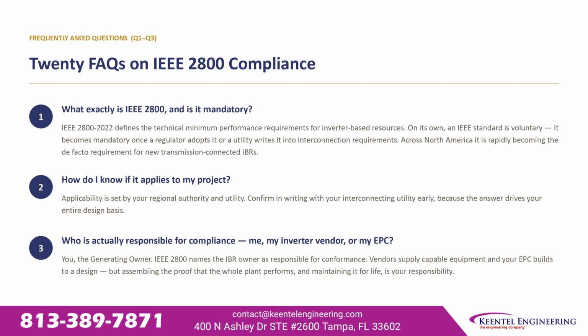How do you know if it applies to your project? Applicability is set by your regional authority and your utility. Confirm it in writing with your interconnecting utility early, because that answer drives your entire design basis. Who is actually responsible for compliance? You, your inverter vendor, or your EPC? It's you, the generating owner. IEEE 2800 names the IBR owner as responsible for conformance. Vendors supply capable equipment, and your EPC builds to a design. But assembling the proof that the whole plant performs and maintaining that proof for life is on you.